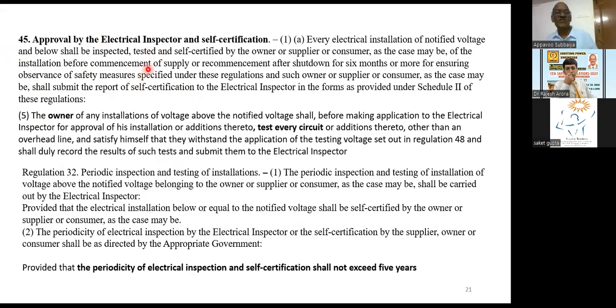While effecting a new connection, what are the things to be done? What instruction is read by the electrical inspector or CESs, according to the voltage limits declared by the state government? In most of the state governments, these vary. In one state it will be 650, another state it will be 11 kV, in another state it will be 33 kV. This is the area where the notification applies, up to which the CESs work. We have to thank Maharashtra. It is the only state which has come out with something on the CES concept. None of the other states in our country has moved even an inch towards it for the past 10 years.